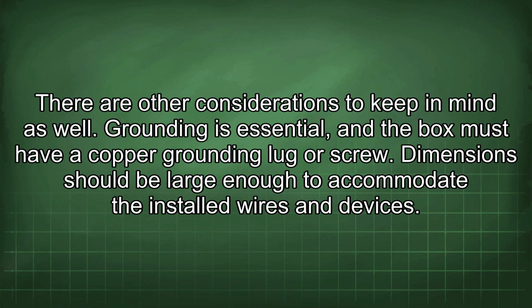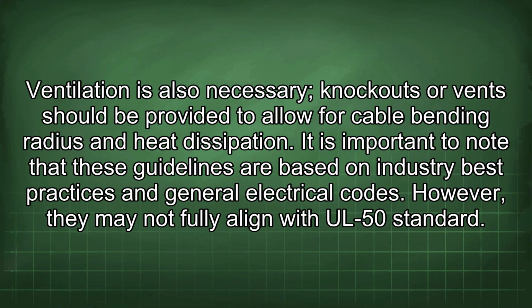There are other considerations to keep in mind as well. Grounding is essential, and the box must have a copper grounding lug or screw. Dimensions should be large enough to accommodate the installed wires and devices. Ventilation is also necessary. Knockouts or vents should be provided to allow for cable bending radius and heat dissipation.